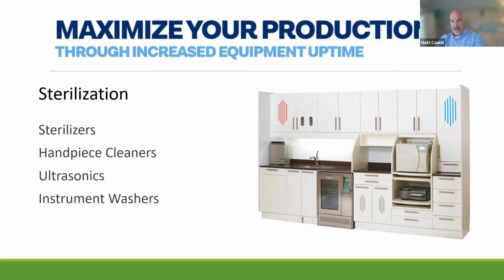In this picture as well, you can see an instrument washer there. Anybody that has those in their office, there's soaps and detergents that need to be changed out on a regular basis. And there's also some filters that need to be cleaned. So you want to make sure that you are using, again, manufacturer recommended soaps and cleaners and filters and so on. It's very, very important to use the right chemicals and the right detergents that correspond with the equipment that you have. In some cases, if you don't, it's pretty easy to tell, and a lot of times it'll void manufacturer warranties. So just make sure that you're using the recommended products.